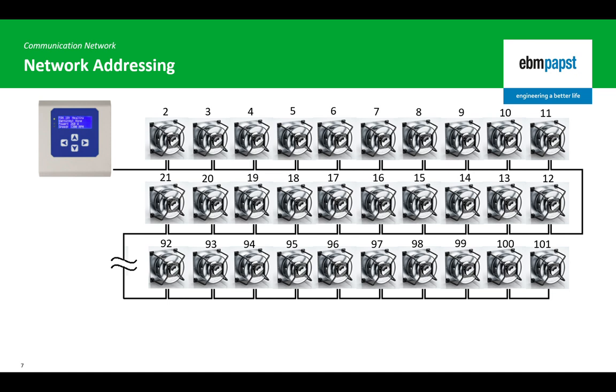To ensure that there is never a conflict between two fans on the network having the same device address, the MDC is programmed to ensure that a fan with device address 1 is not permitted. If a fan with device address 1 is added and detected on the network, the MDC will recognize it as a new fan and will prompt the user to define whether it should be added to the network.